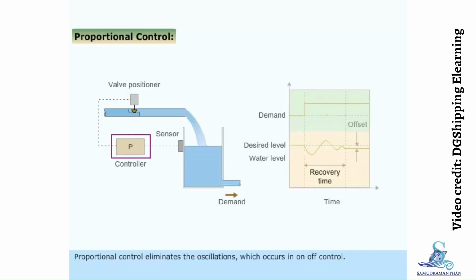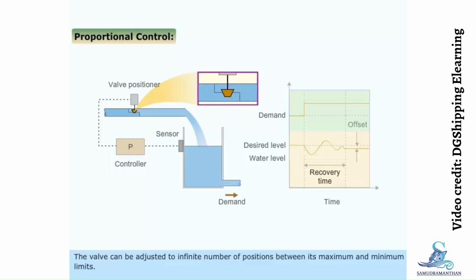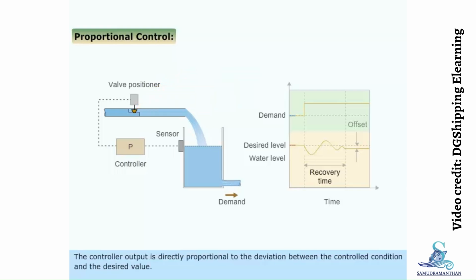Proportional control eliminates the oscillations which occur in on-off control. The valve can be adjusted to an infinite number of positions between its maximum and minimum limits. The controller output is directly proportional to the deviation between the controlled condition and the desired value. The opening of the valve will depend on the extent of increase or decrease of water level from the desired level.